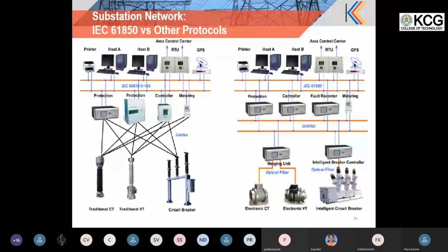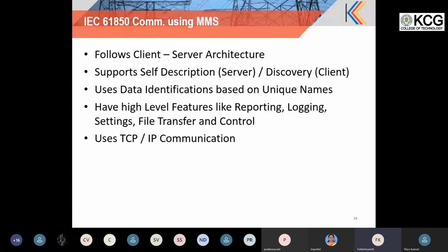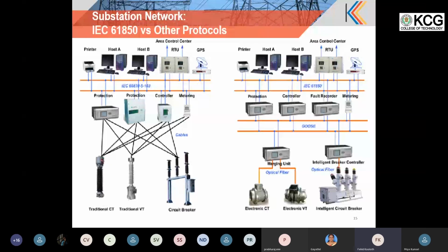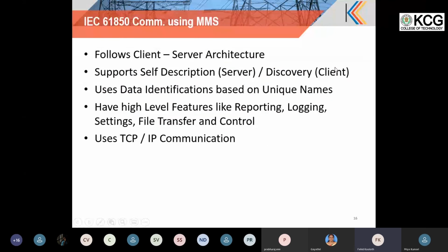Moving on to the MMS. This is the overall architecture we have mentioned, and MMS is used for data transfer between the bay level equipment and the station level equipment. It is actually a client-server architecture over the TCP/IP communication layer. If you know the OSI ISO layers, you will get a TCP/IP communication layer, and MMS sits over that. It has a client-server architecture in which multiple clients can connect to the server, and once the connection is established, it is like a pipe laid between server and client, and data transfer can happen through the pipe.